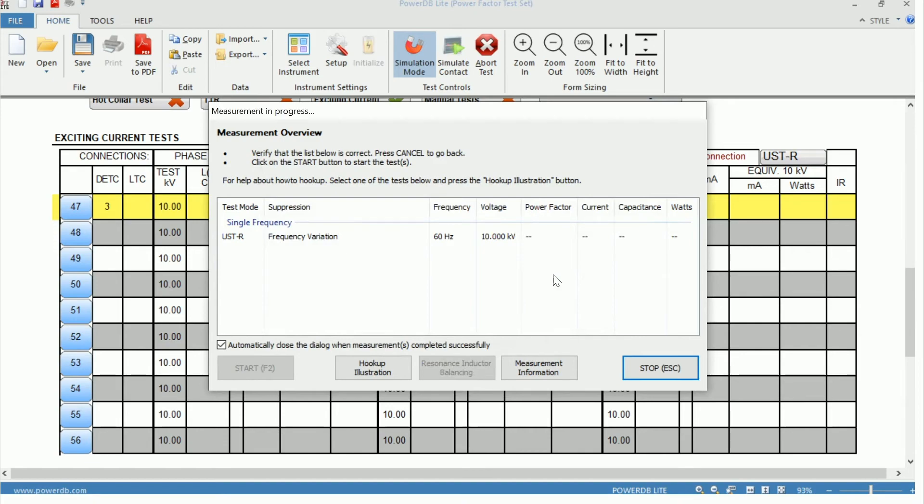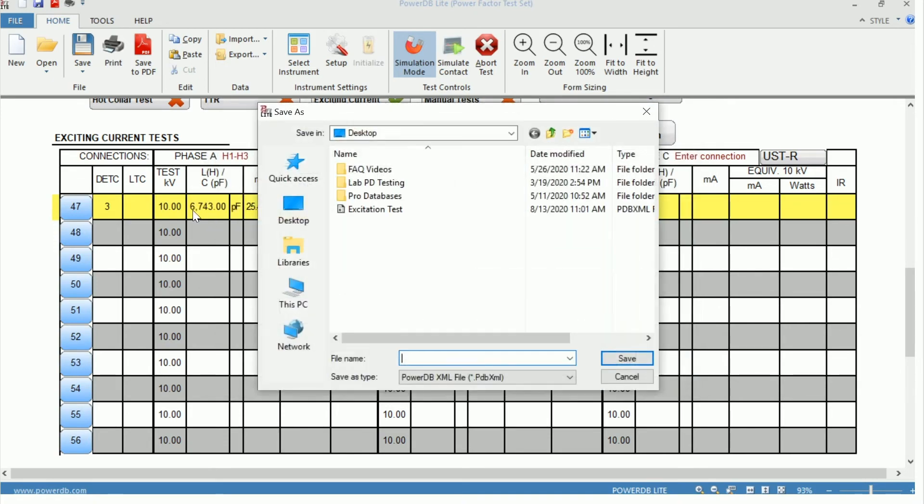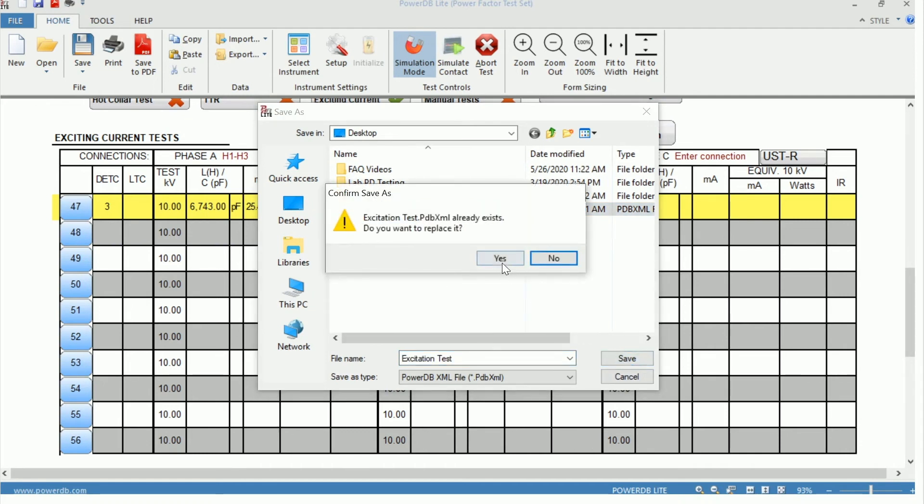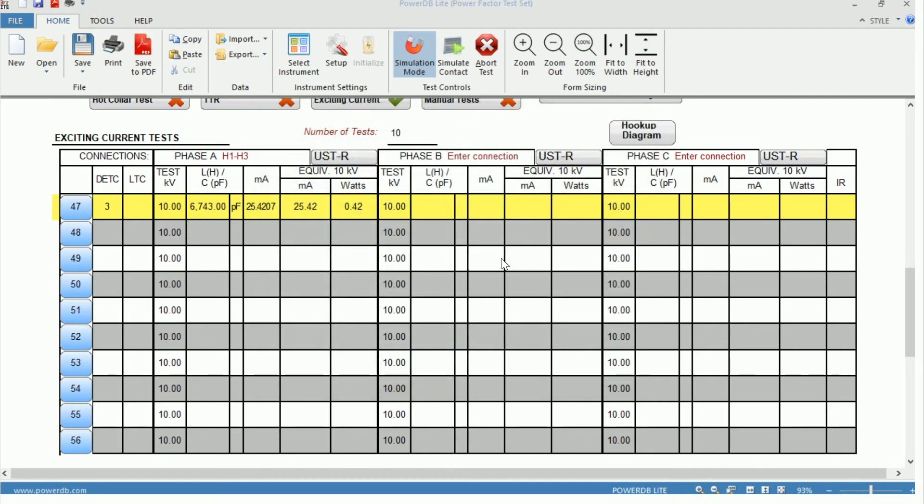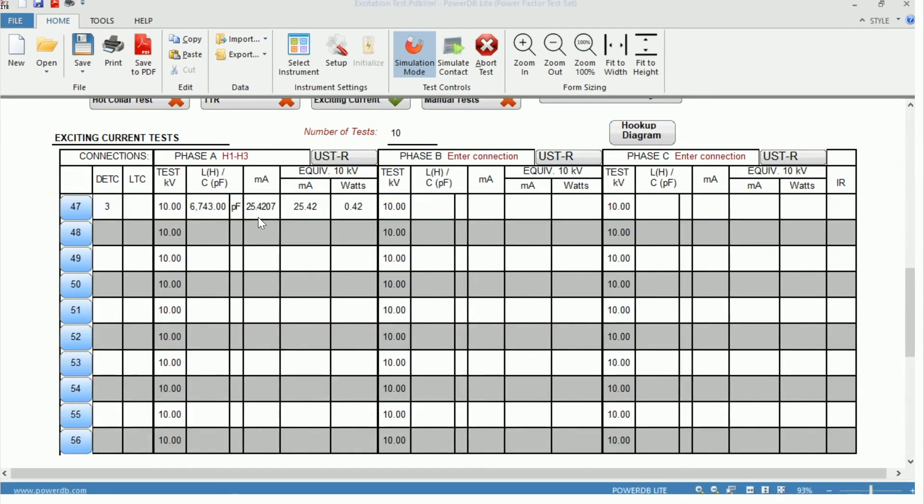So the measurement is in progress, as we can see in the top left. And the measurement has taken place. It allows us to save the document. So we can overwrite that and save. So it's a one-time save. And now we can move forward with testing, and it will just update that document as we move forward. So looking at our measurement, we can see we have our capacitance in picofarads. We have our excitation current, which is 25.4 milliamps, and our 10 kV equivalent, which is equivalent to the actual measurement we got since we were testing at 10 kV.